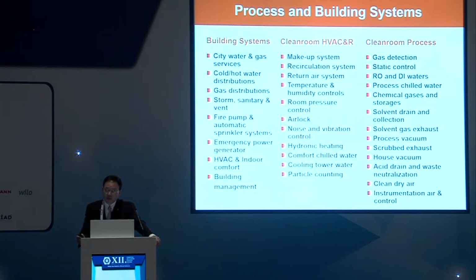Now for clean rooms, it is very interesting. Typically, we use the airflow to control the room temperature and humidity, right? We also use the supply air, return air, and exhaust air to control the room pressure. But we also use the supply air to control the room concentration. So once you change the supply airflow, the impact on the room condition is far beyond temperature and humidity. You change the room pressure relationship, and you change the room concentration in terms of the cleanliness class.